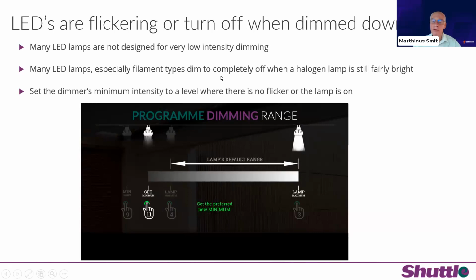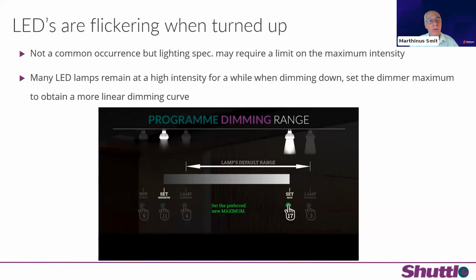Then we find that some LEDs flicker when they are dim or when they reach a minimum intensity. It's interesting that many of the lamps are designed for European conditions and are not designed to dim so low, and we do find that sometimes you get a low-end flicker. We also find that some of the lamps actually turn off completely when the dimmer is still very bright. That is a very common characteristic of especially your filament lamps. So in that case, you must be able to set your dimmer minimum intensity to higher than factory default. Then it's a rare occurrence, but you do get some LEDs which flicker at dimmer maximum intensity, and we still can't really figure out why that happens.